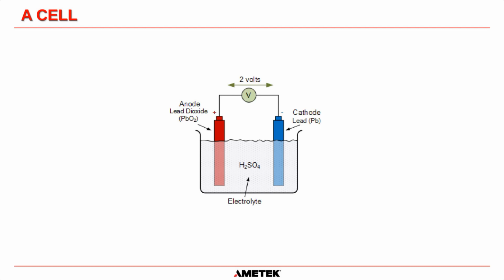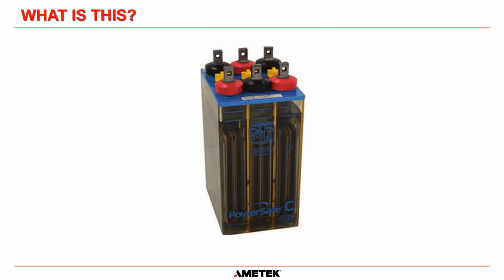Two things happen as it gets to the end of discharge on a battery. The cathode, the negative plate, has a lead sulfate layer on it now, which makes it very difficult for it to use the electrolyte, and the electrolyte solution has a much lower specific gravity because all of that acid has been absorbed into the negative plate. When you recharge it, it's basically the opposite. The lead sulfate on the negative plate is expelled back into the electrolyte solution, and we revert to having a fully functional electrolyte, with little or no lead sulfate on the negative plate after we have recharged the battery. Hopefully that didn't confuse you too much, because I think I may have confused myself a little bit. But that is the most basic operation of a lead acid battery.